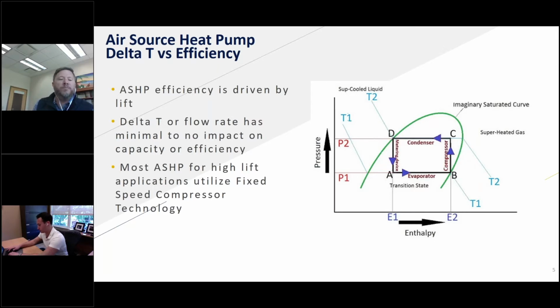Now, there is some small impact, I would call it marginal at best, with the heat transfer that happens within a unit, within the heat exchangers themselves, whether making hot water or chilled water, as we transfer energy between the refrigerant and the water. There is some slight benefit, but as I said, it is marginal. So it really doesn't add any value to have a wider or a smaller delta T. From a pumping perspective, there is some value in a larger delta T; you get slightly lower pump energy. But at the end of the day, what's really driving the efficiency of the building is the prime movers, the heat pumps, the chillers, the boilers, and that's where the lion's share of the energy is.